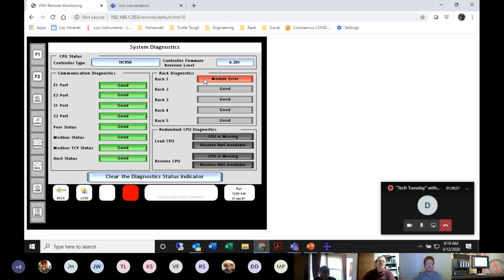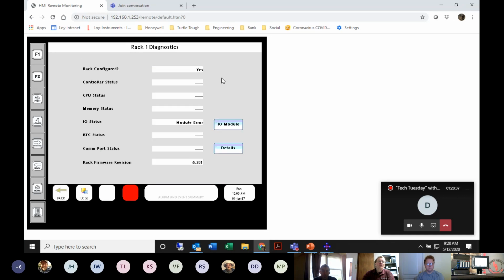Now, if you look over here on the right-hand side, on rack 1, which is the only rack I have communicating right now, we have a module error. If I click on the module error, it takes me to rack 1, and it tells me everything about that rack. It says, is the rack configured? Yep. How's my controller? It's good.